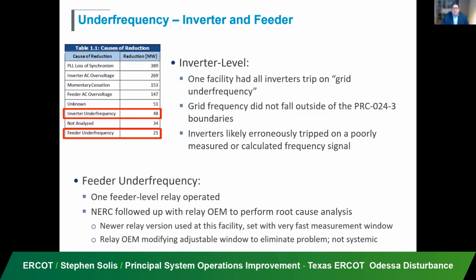Now, when we look at some unknown causes, the real takeaway here is it is so important to have high resolution data. Simple SCADA data, 4 to 10 second type data, is not sufficient. You need data within cycles and potentially at multiple locations. At the point of interconnection, what was the system doing? Inverter oscillography, what was the inverter doing? Perhaps you have digital relays that can capture data, or fault recorders, perhaps on the low side in the feeder collection system. By being able to look at all these data sets, you're better able to understand the interactions between the inverter controls, the power plant controls, where was voltage on the high side versus the low side of the step-up transformer. Without that diagnosis, it gets rather difficult trying to understand what happened because it's all happening within cycles.